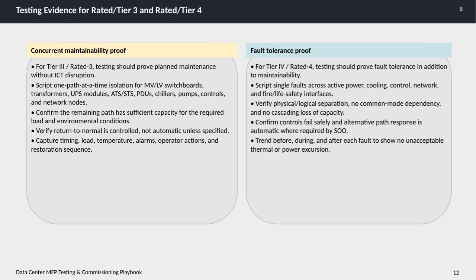Moving on to Tier 4 or rated 4, the testing requirements build on Tier 3 by also proving fault tolerance. This involves simulating single faults across active power systems, cooling, control systems, network, and fire or life safety interfaces. The test must verify that physical and logical separation is intact, ensuring no common mode failures and no cascading loss of capacity. Controls should fail safely, and automatic responses via alternative paths should activate as required by the Sequence of Operations. Importantly, trend data before, during, and after each fault must be analyzed to confirm there are no unacceptable changes in temperature or power levels.